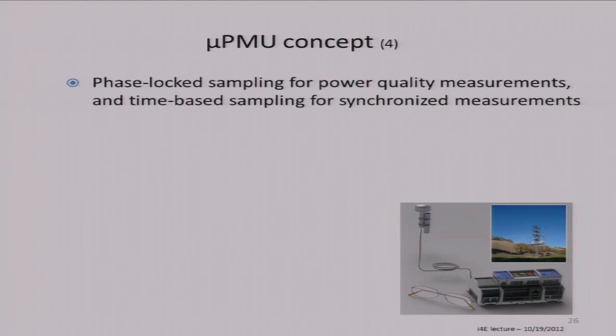For those of you interested in the instrumentation, there's a really interesting challenge: when you're doing power quality disturbance measurements, it's really important to get 2 to the n samples per time interval, typically a cycle or 12 cycles, so you can do harmonic analyses without any bleeding over the edges when you do a Fourier transform. If you have 2 to the n samples in the time interval, that's very useful for the analysis.